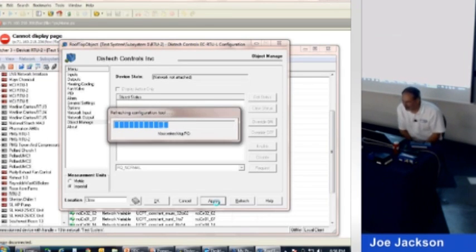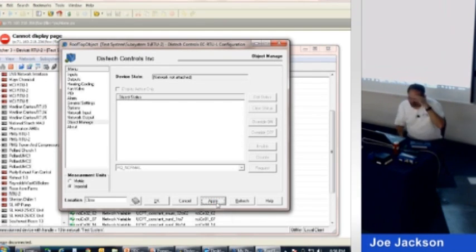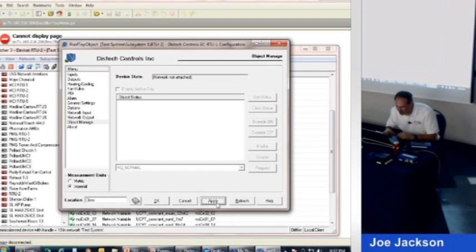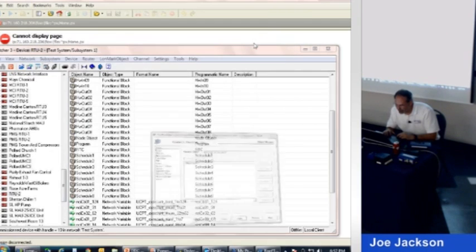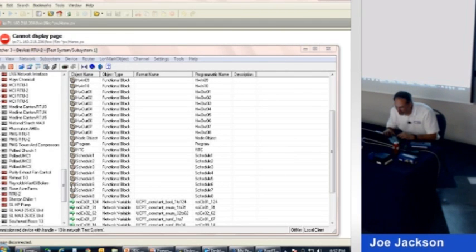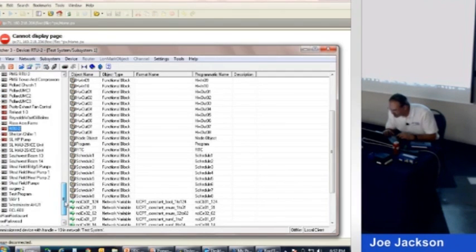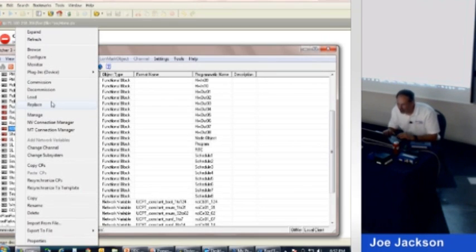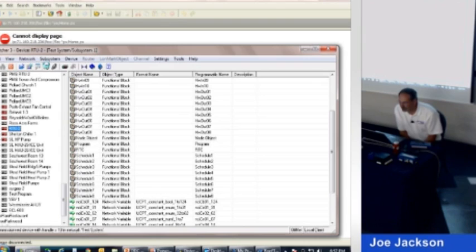And this little startup program that we use is really nice. So we programmed this rooftop unit. Now we're wondering if it's really working or not. So there's two parts to this. One part is the configuration. Find the one that we're doing here. Let's see. Yeah. And if I want to see what the unit's doing, we call this monitoring. It takes all the information that we just put into the controller and draws us a pretty picture. Now the controller's not really there, so it's not going to have real live data on it. Hopefully it's going to open up here in a second. There it goes.